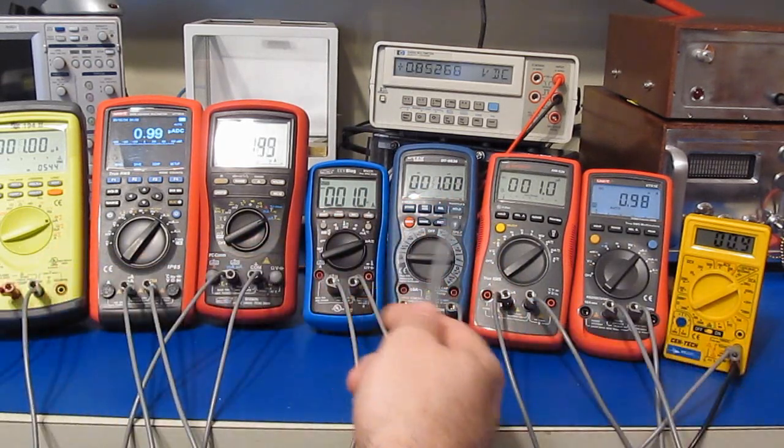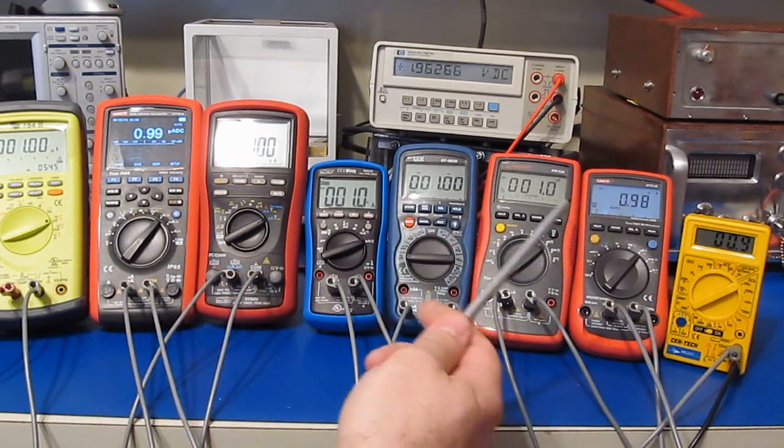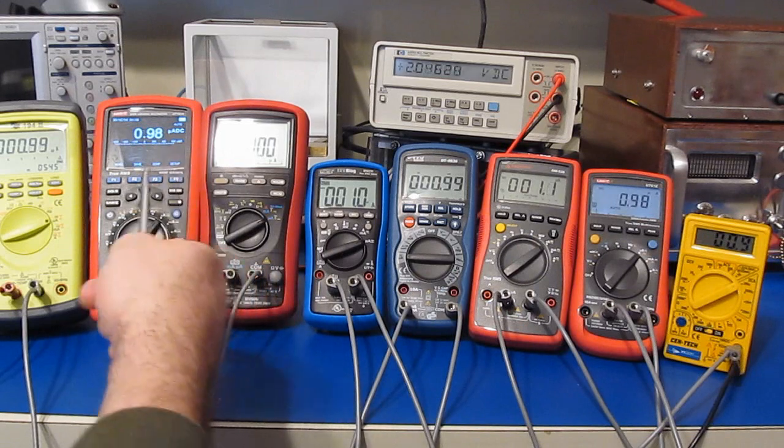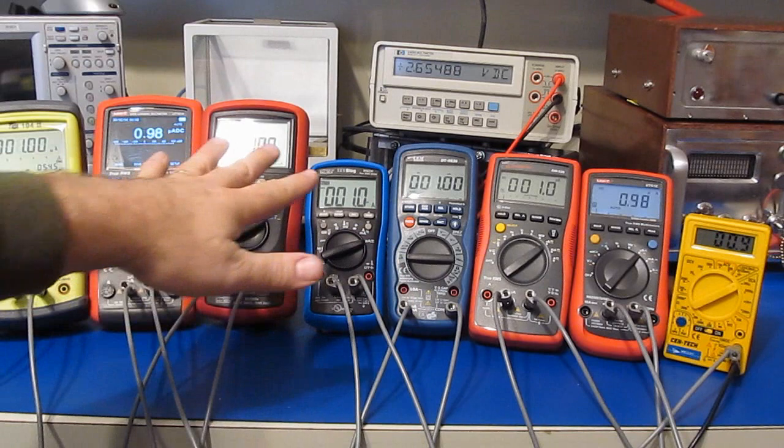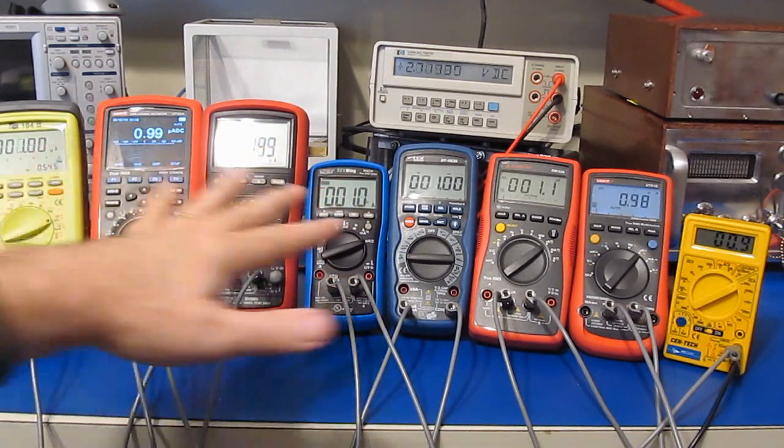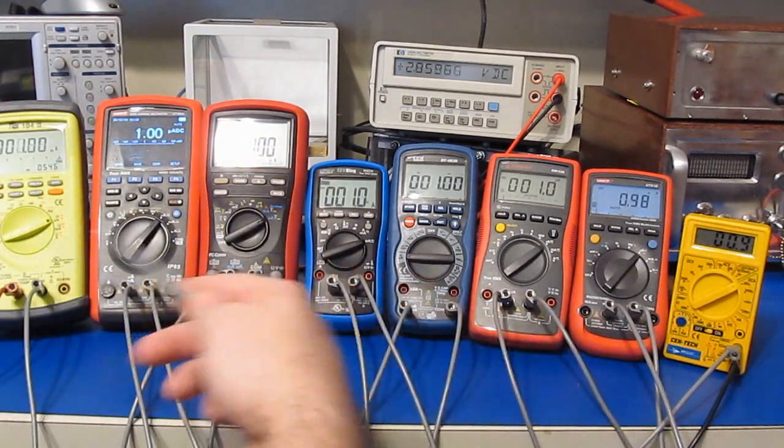I have them all set up in series. They're currently attached to my Fluke reference. What I've done is I placed a series resistor in line with them and I've adjusted that value to give me roughly one microamp of current.